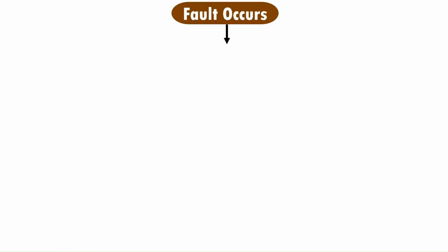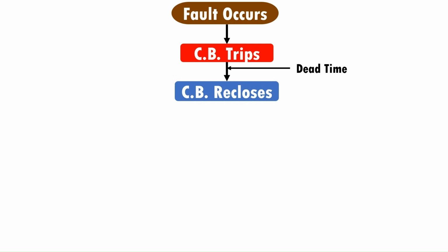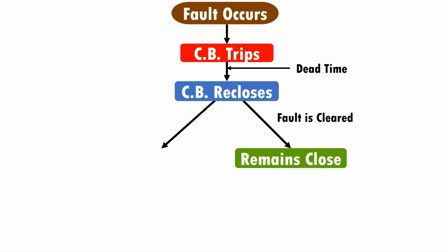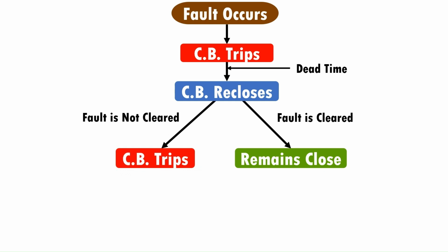When a fault occurs, the circuit breaker opens its contacts. Also, the auto recloser detects the fault. The recloser waits for a predetermined time before attempting to close again. This waiting time is called the dead time. After the dead time is over, the auto recloser automatically recloses the contacts. If the fault is cleared, then the contacts remain in the closed position. But if the fault is not cleared, the circuit breaker will trip again and open its contacts.